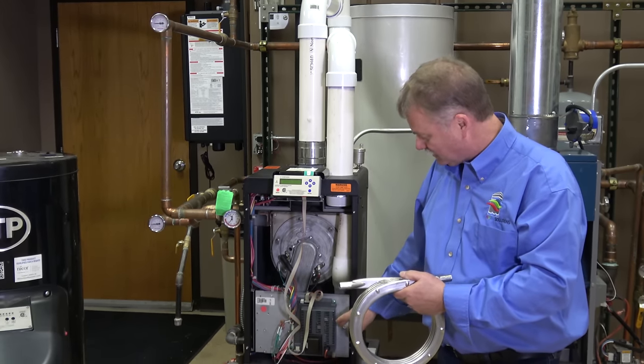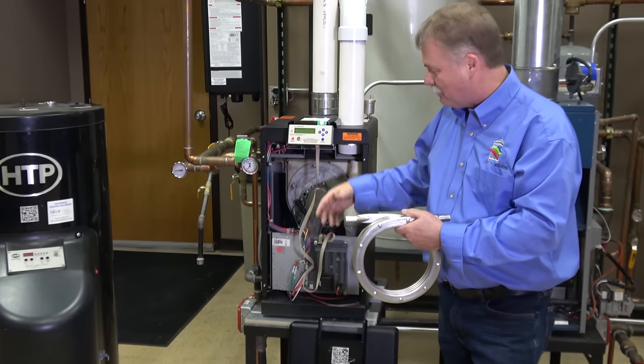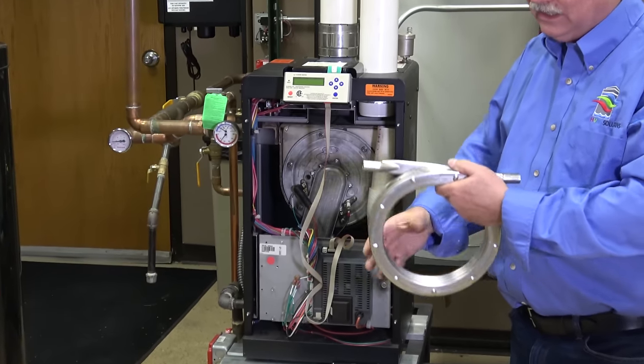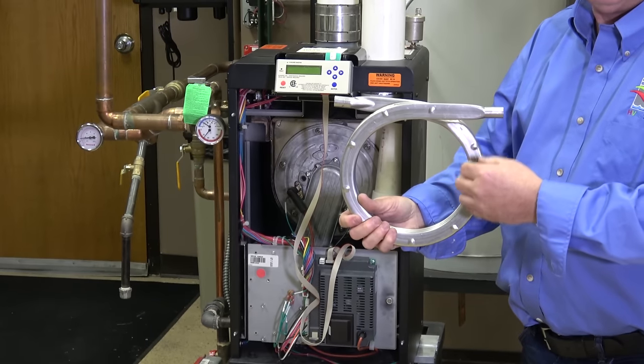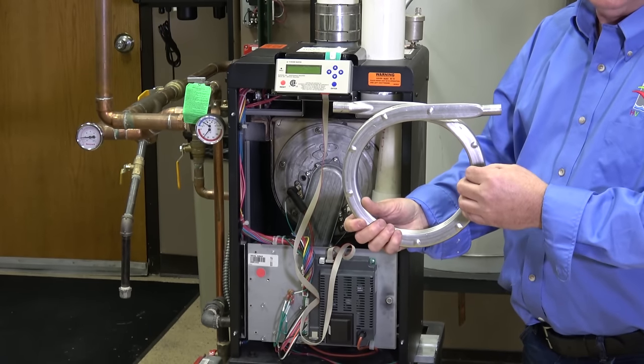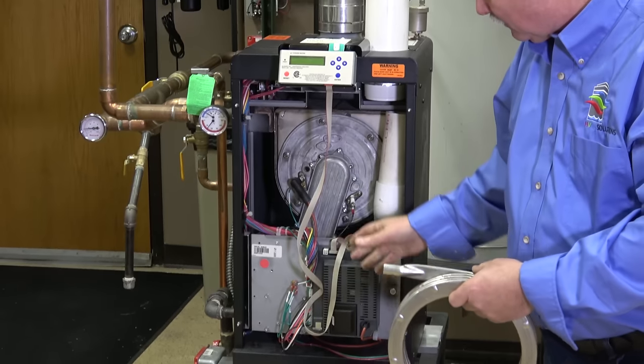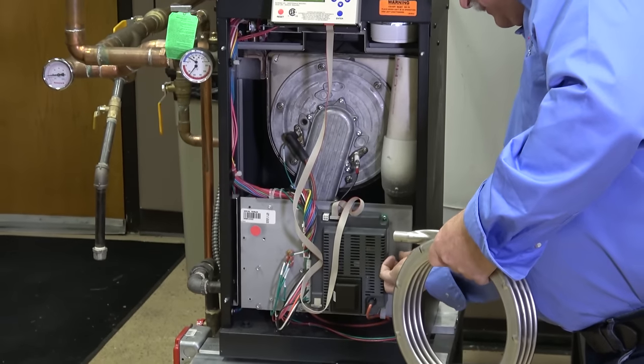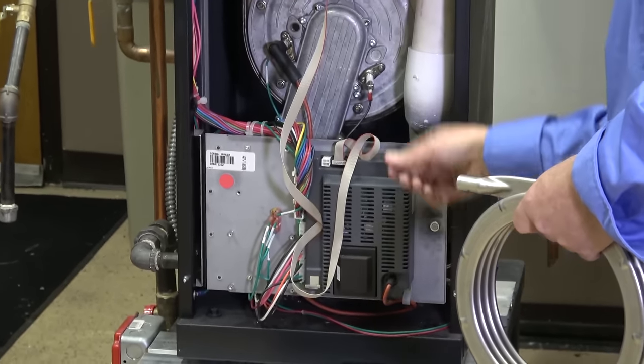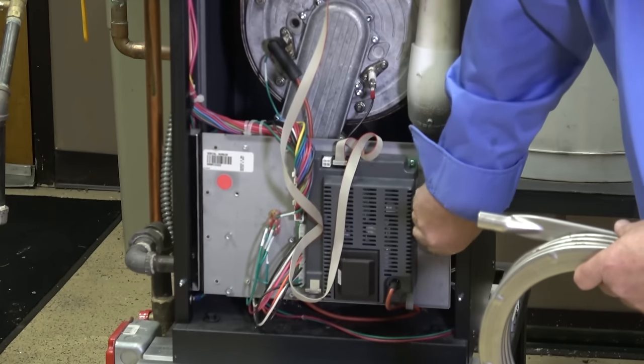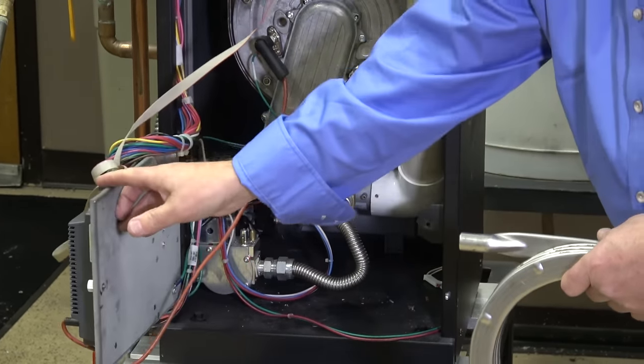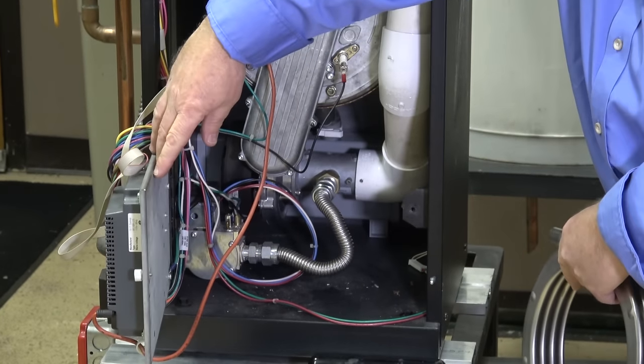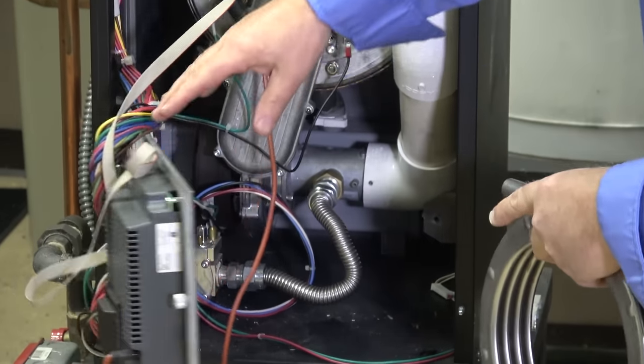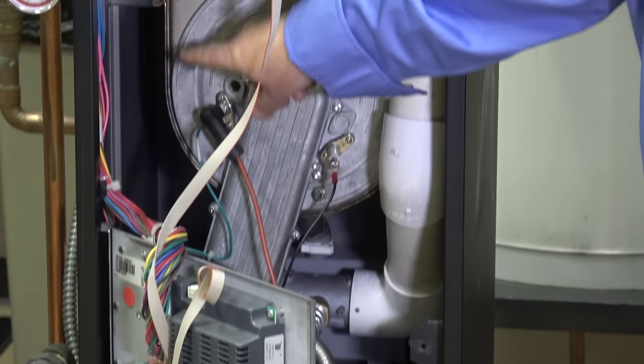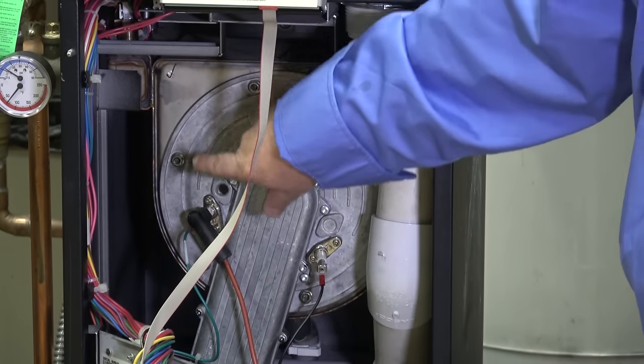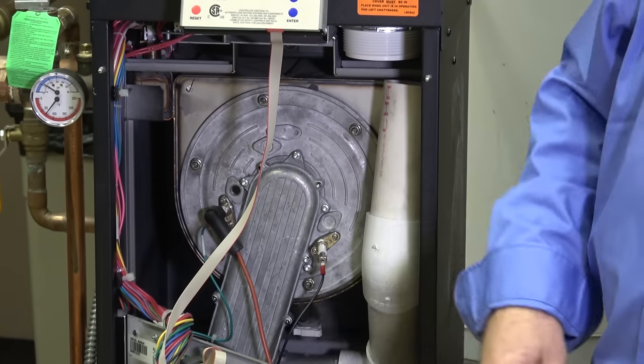On the front, yes, there's a little computer board here. This is monitoring everything that's going on with this boiler. It adjusts the flame and everything else to try to maximize the energy efficiency of the unit. Behind the control board, this little door here, you have your typical gas valve, your burner, this is the burner section here, and this little 80,000 BTU boiler, that's the whole heat exchanger.